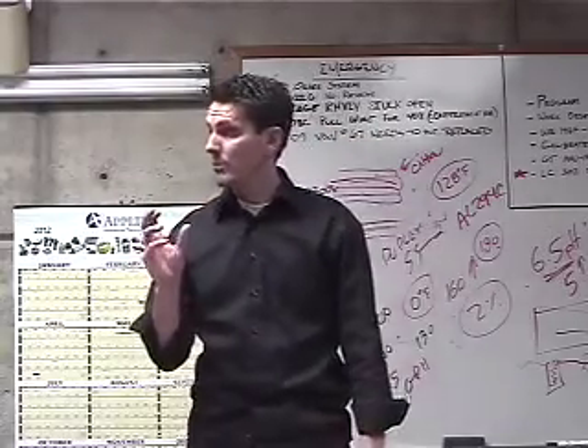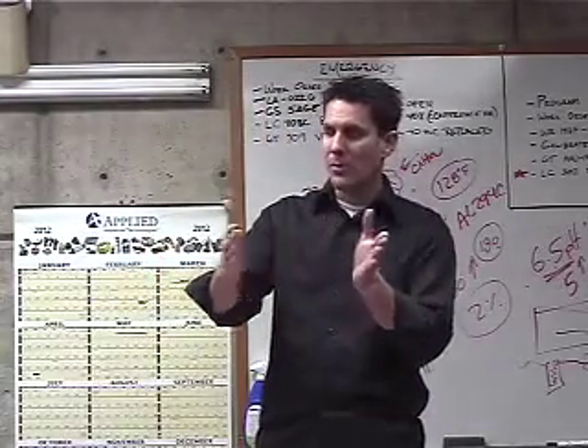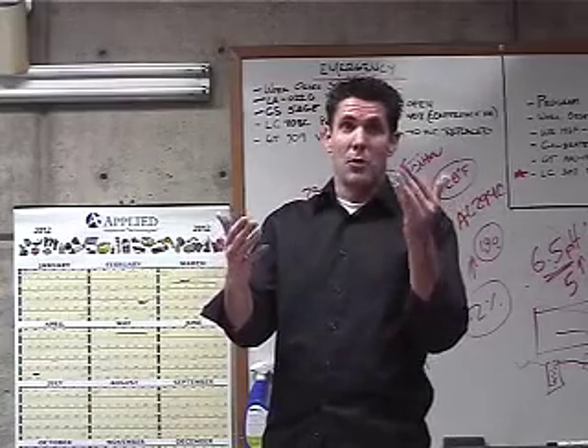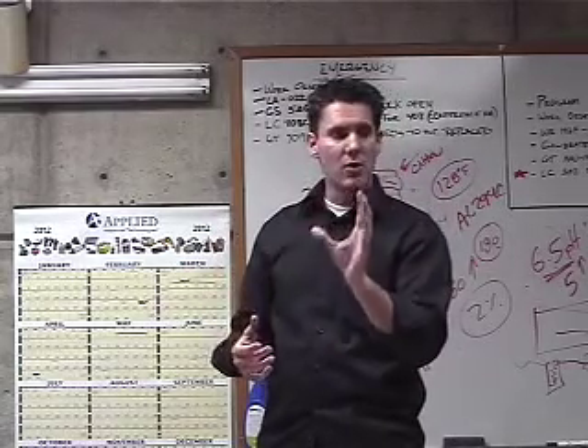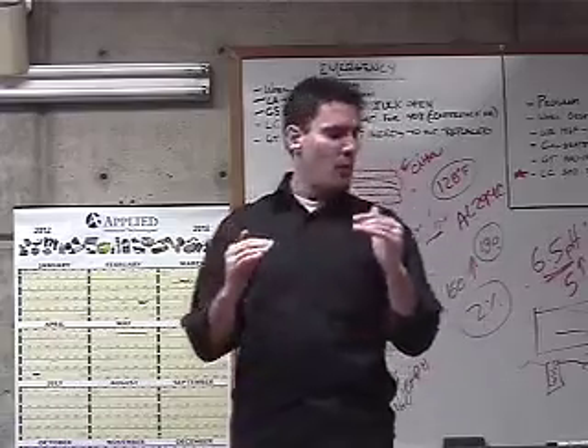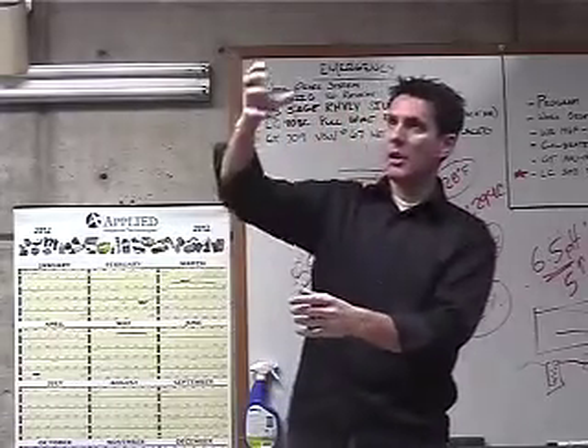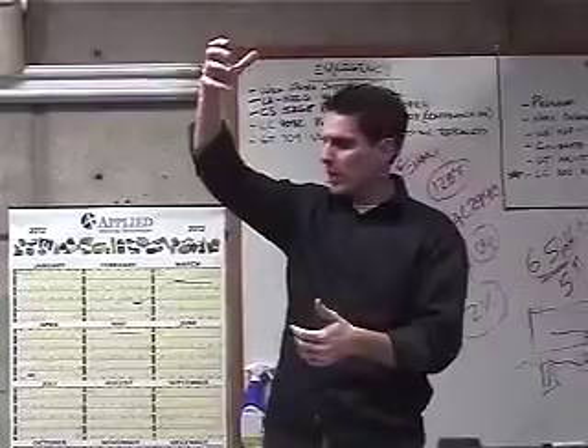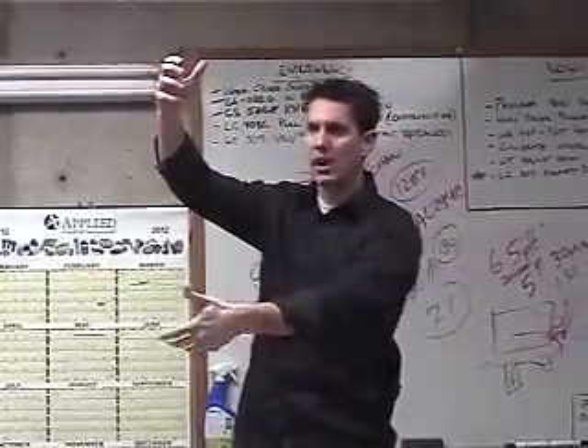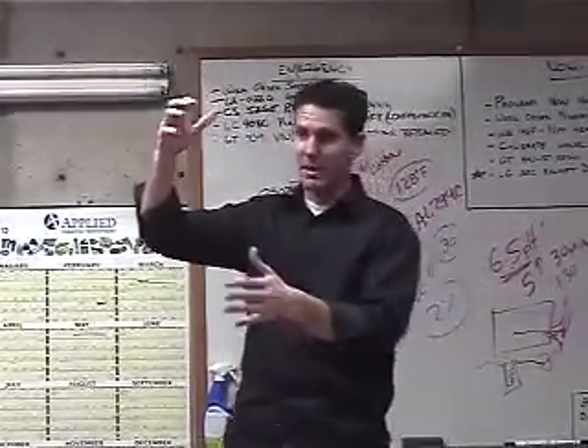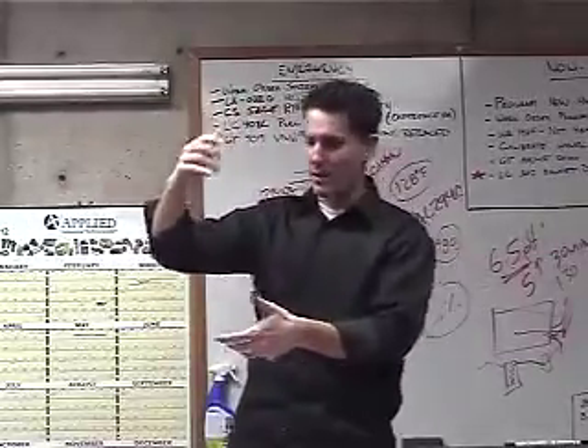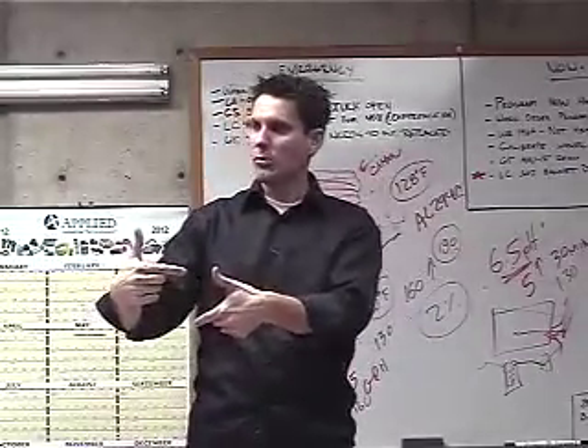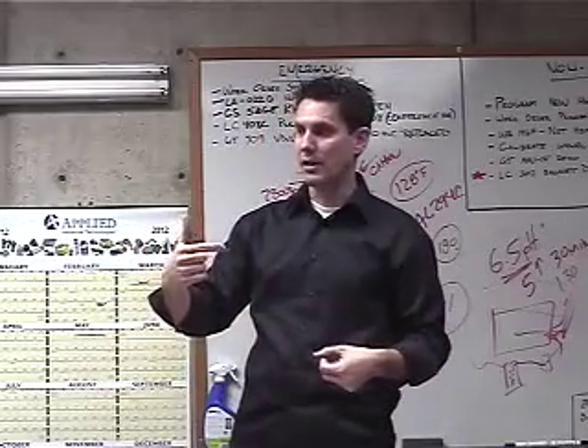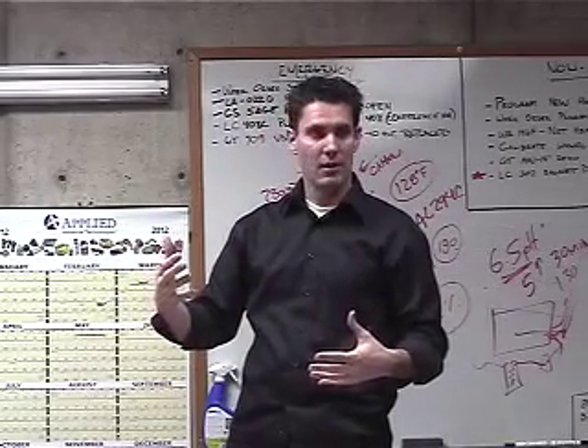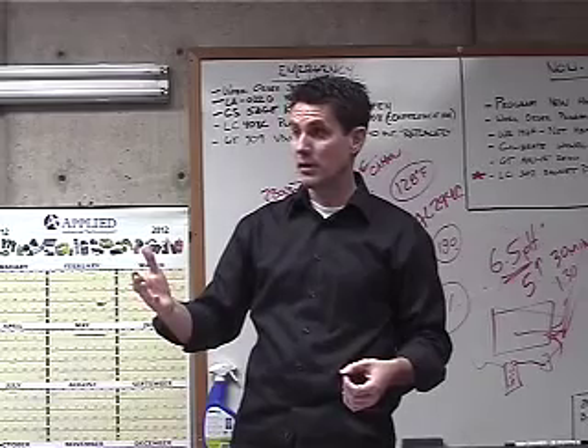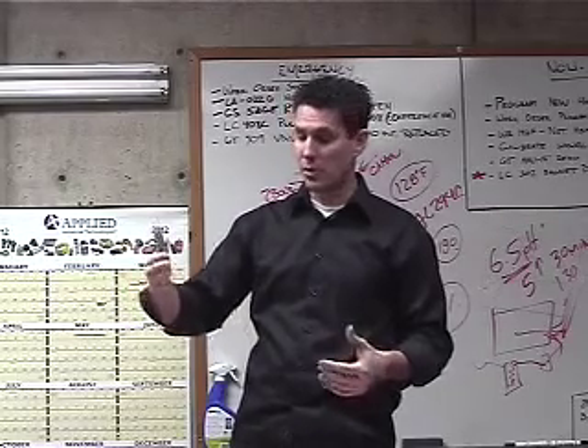Okay, that becomes very important because as you start to get outside of these normal operating windows, which happens, you know, the way these things are vented, these new high efficient boilers are so temperamental. What happens? My stack is coming out. Your vent is going off the roof, right? Where are you guys pulling your combustion air in from? Sidewall? Okay, good. I mean, not good, but that's a perfect example of what's going to happen. The wind starts blowing against that wall where that vent is pulling the combustion air in, what happens? Is your combustion going to change? You betcha. Because we just changed the air pressure.